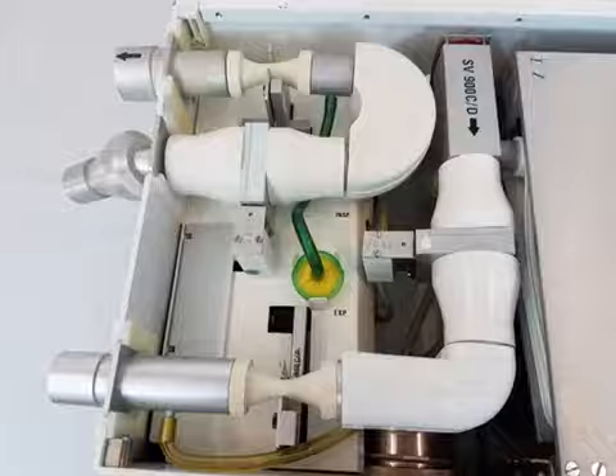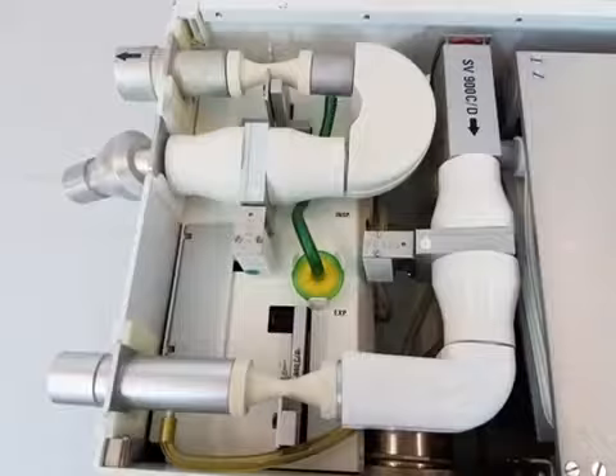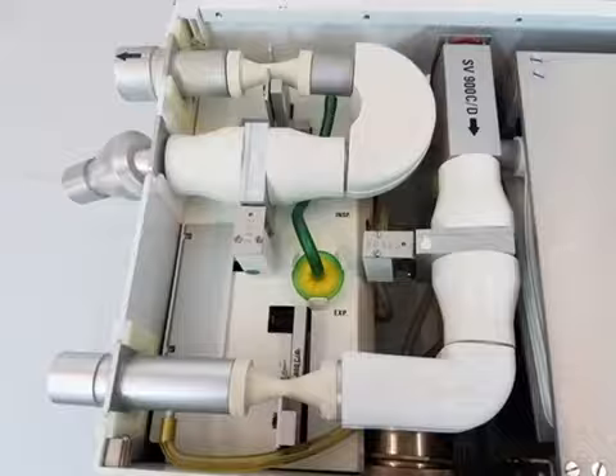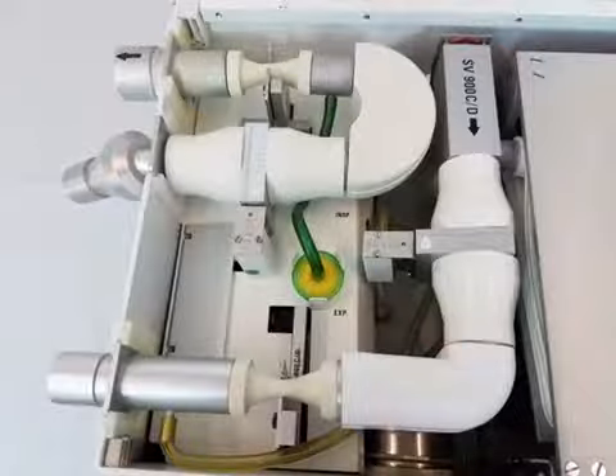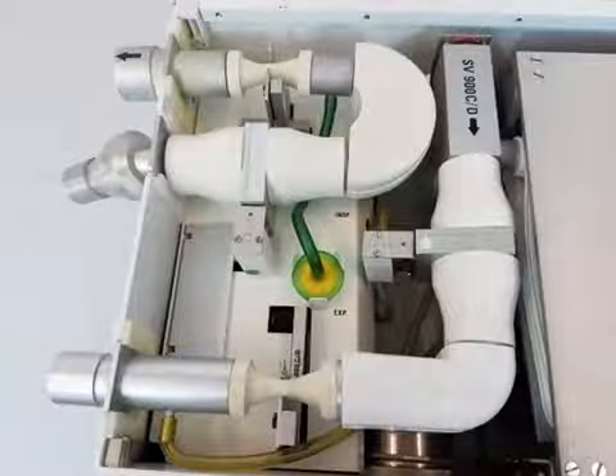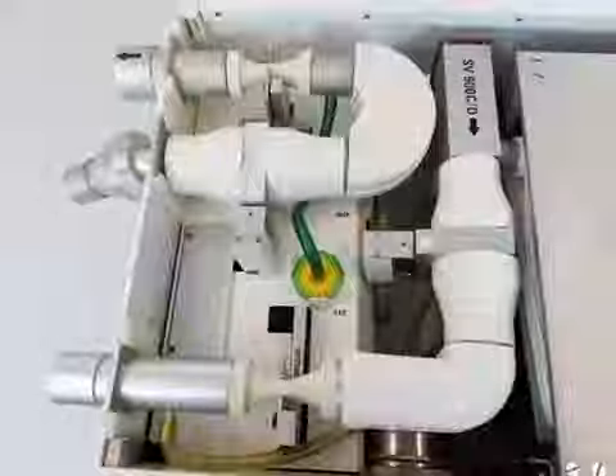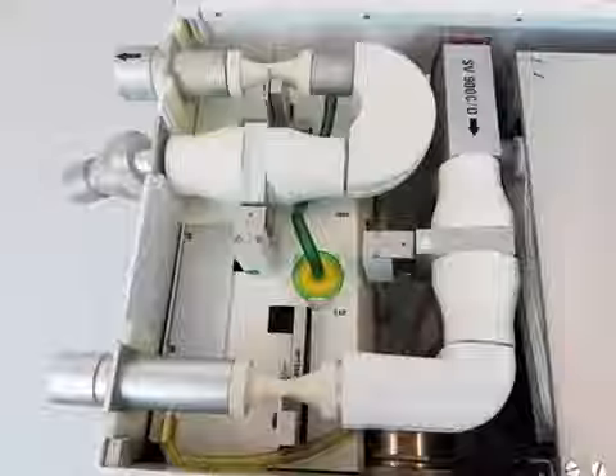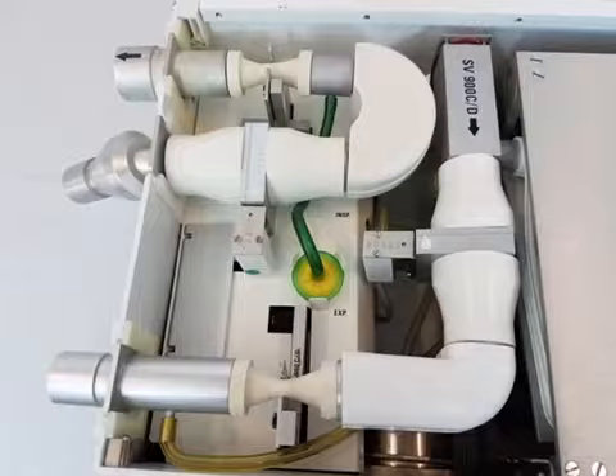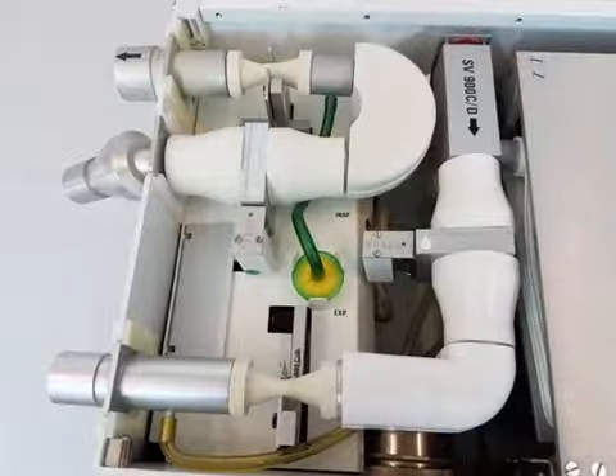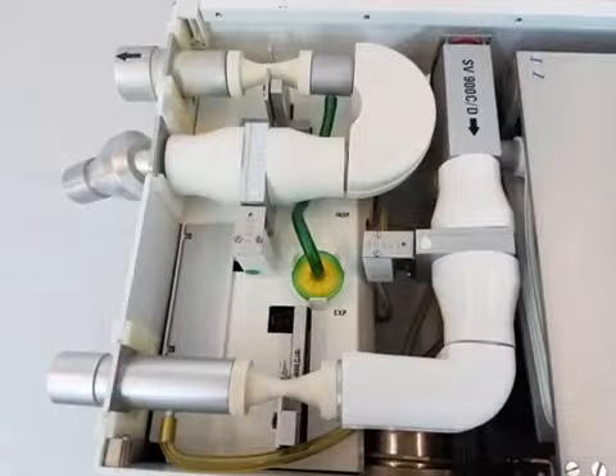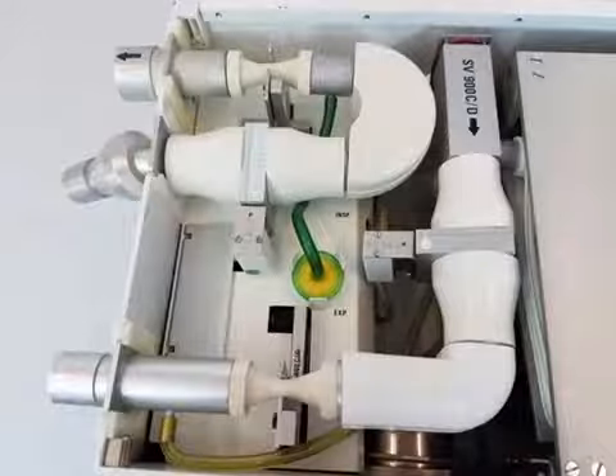This is my expiratory flow transducer, and it measures the gas flow from the patient. To prevent condensation, the transducer is heated to approximately 60 degrees Celsius. Then we have over here this green thing. This is my expiratory pressure transducer, and it measures my airway pressure. Then we go around the loop and we get to my expiration valve, or expiratory scissor valve, which is another nickname for it. This is closed during my inspiratory phase. During the expiratory phase, it's either fully open or partly closed to regulate my PEEP level, whatever I have my PEEP set.